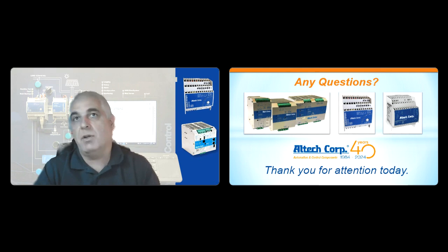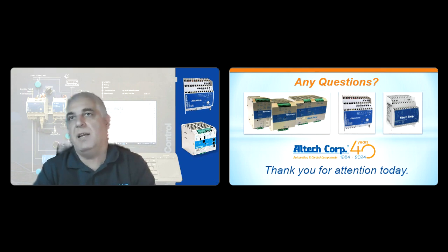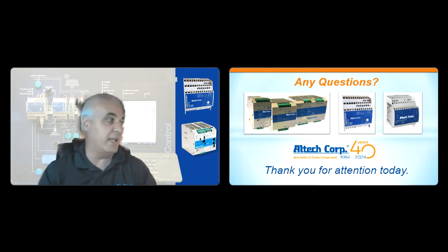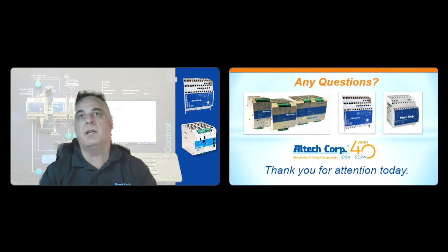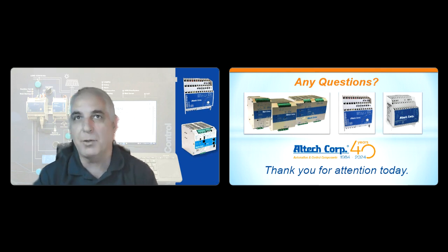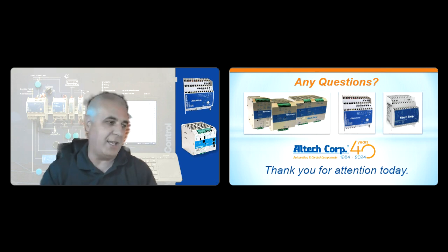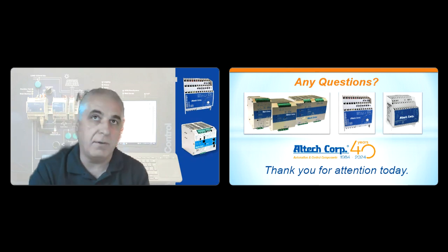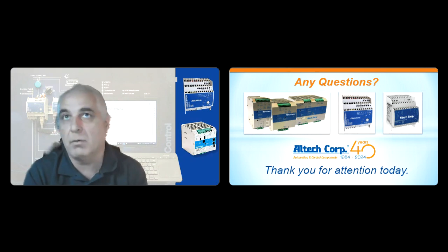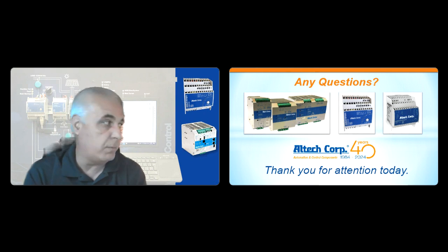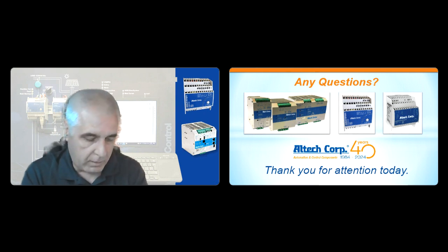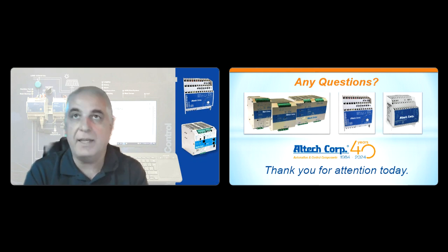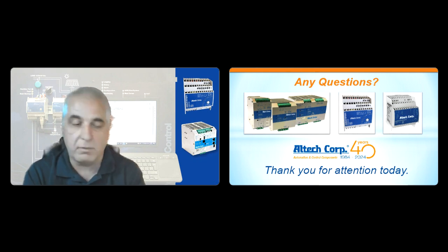One thing came to mind: a jail came to us and said, hey, we have a problem. The battery goes out and the doors cannot be locked in the jail when the power is out. So we had to build a system with huge batteries, I think they were like 450 amp hour batteries, and we had to connect a couple of chargers for this UPS in parallel to make sure it can handle all that big power. But there is a solution for that as well.